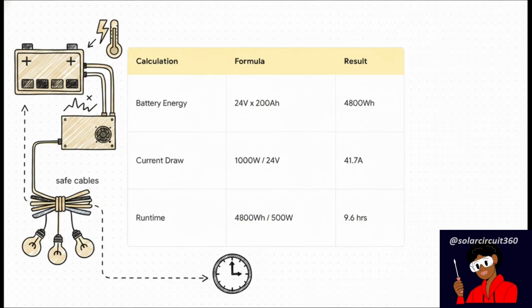Think of voltage like water pressure in a pipe and current as the physical size of that pipe. If we multiply our 24 volts of pressure by our 200 amp hours, that gives us our total energy pool of 4,800 watt hours. Then, say we're pulling a heavy 1,000-watt inverter load. We divide that by 24 volts, and we know we need thick enough cables to safely handle a 41.7 amp flow without getting hot.